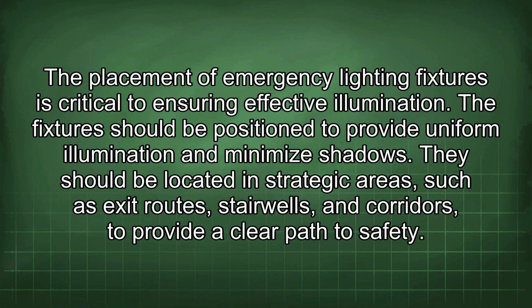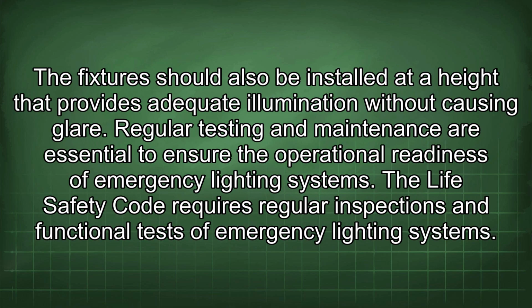The fixtures should be positioned to provide uniform illumination and minimize shadows. They should be located in strategic areas such as exit routes, stairwells, and corridors to provide a clear path to safety. The fixtures should also be installed at a height that provides adequate illumination without causing glare.